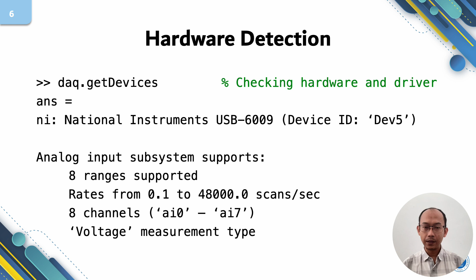The type of measurement is voltage. So the sensor we can connect directly to the analog input of the hardware is voltage type. Some sensors produce milliamperes, or electrical current. So be careful, never connect any current measurement type sensor to this device. It is harmful for the device.